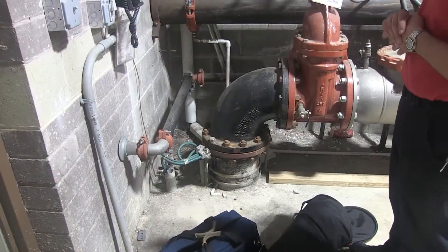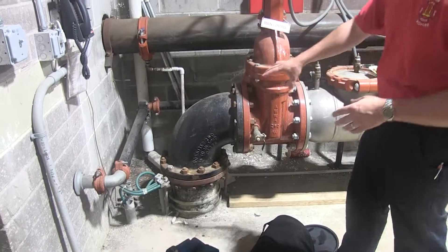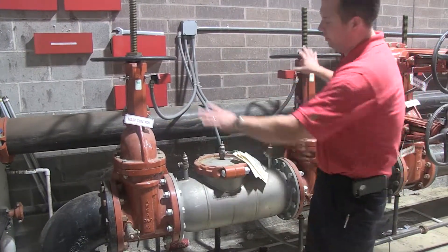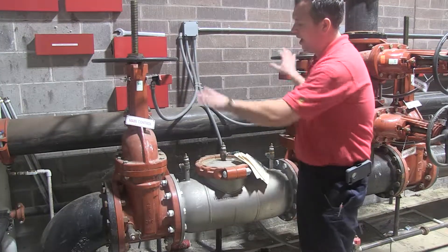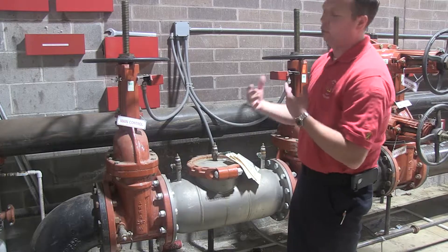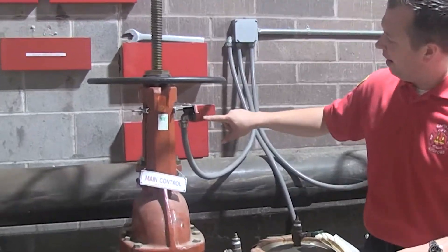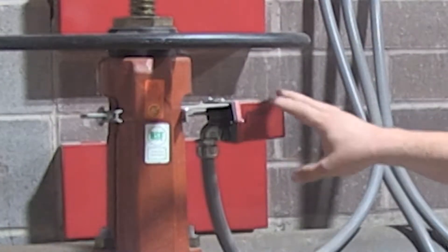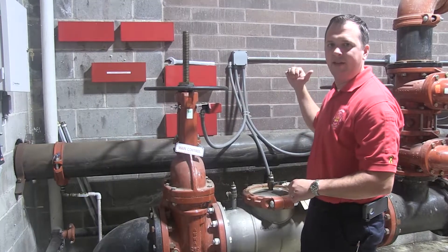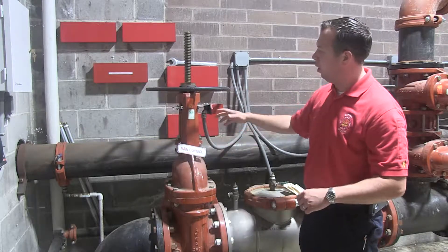Regardless of what type of system you have, it all starts with the water supply. We're on city water here at Lowe's, and you can tell water is coming up from the ground. The first set of valves you're going to see are the main control valves. Sometimes you'll see one labeled city side and system side — there are two valves here because this is a backflow preventer, and these valves are here to help service it. Spinning either one of these wheels shuts off water to the system. All valves will have a monitoring module nearby because the fire alarm system supervises the sprinkler system.